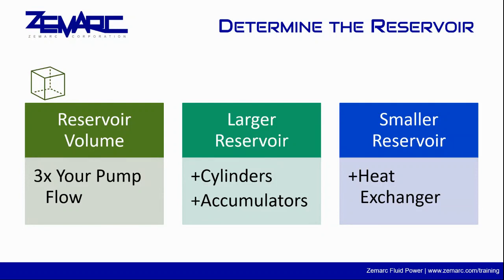The bigger the reservoir, the more heat and air can be dissipated from the system, but the more space used. The reservoir size can be decreased by adding in a cooler to improve heat loss. The reservoir size will need to be increased when adding large volume adders, like cylinders and accumulators.